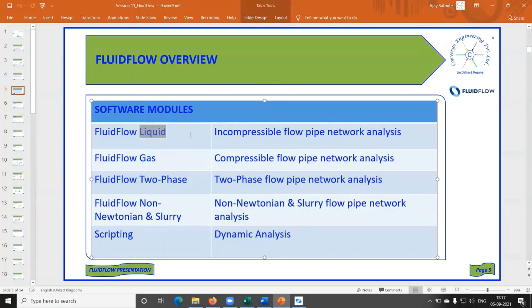For a compressible gas or compressed air supply system, you use the Fluidflow gas module. For a two-phase system — like oil coming out of a well containing oil and gas — you use the two-phase module for pressure drop calculations. For fluids that are non-Newtonian or slurry, like sand and water, you use the non-Newtonian slurry module. For simple dynamic analysis such as determining how long it takes to fill or empty a tank, you use the scripting module.